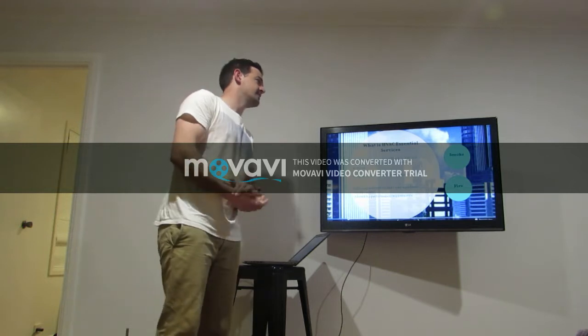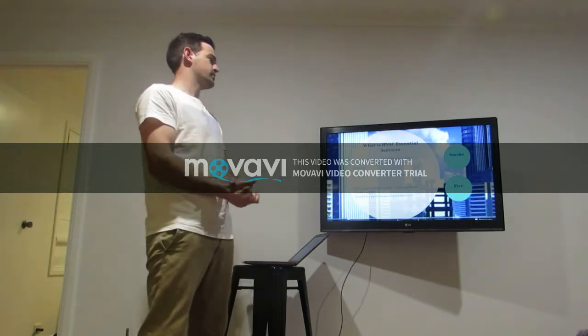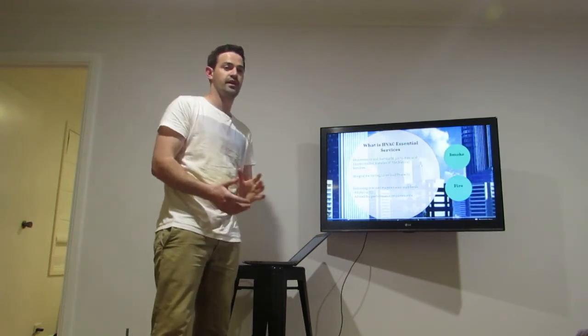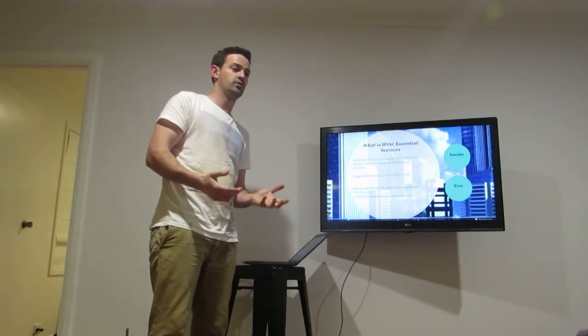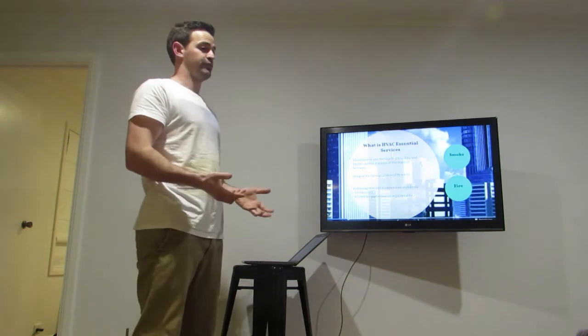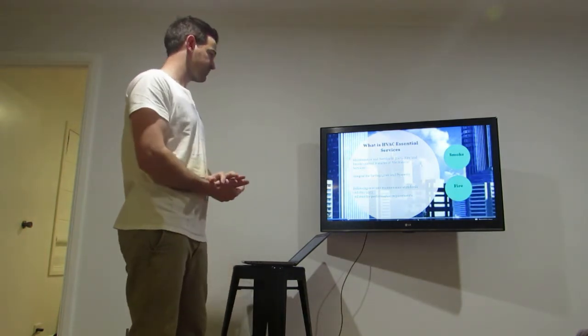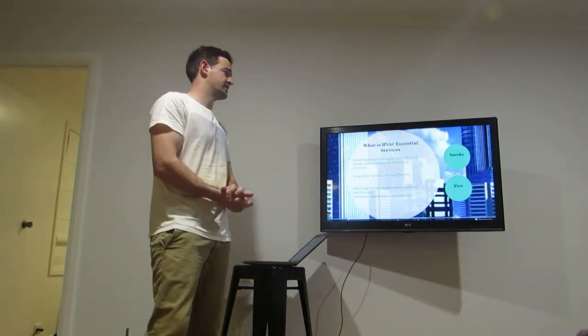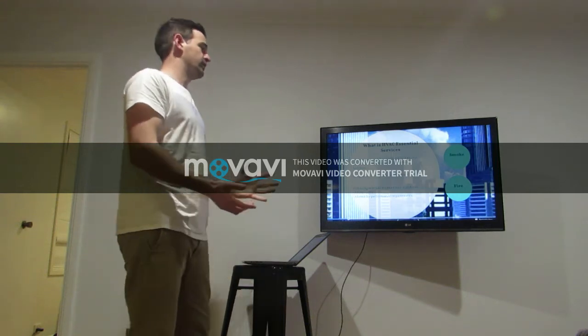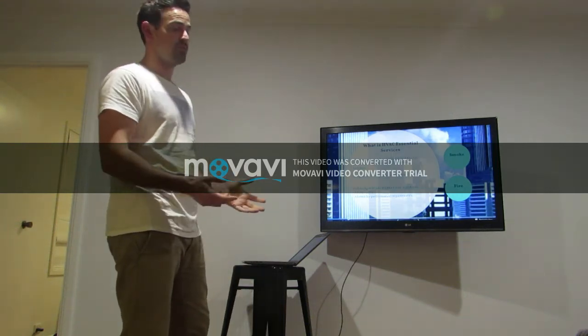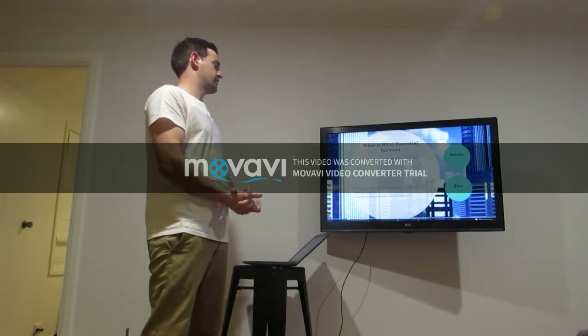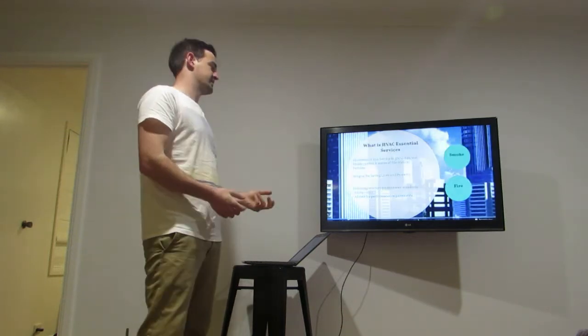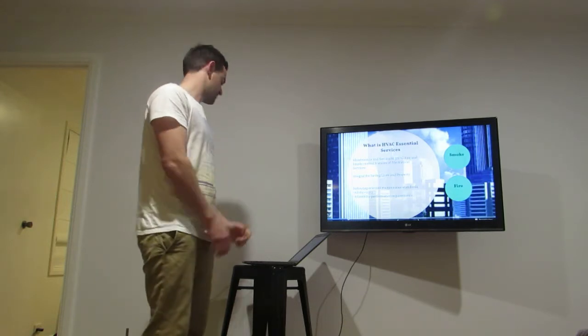So what is essential services in HVAC? This is the maintenance and service of HVAC fire and smoke control features of mechanical services. This is all the equipment that is used in fire or smoke control if a fire alarm does go off. This is integral for saving lives and property. The relevant standards that we follow for all of our maintenance and service tests are AS 1851-2012 and AS 1668 for the performance requirements.